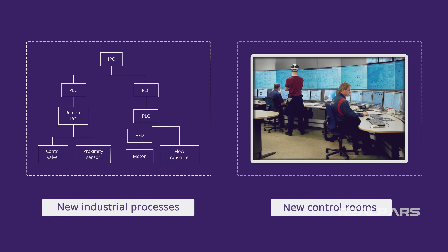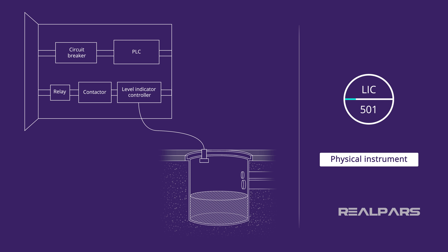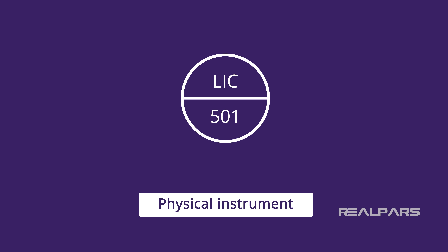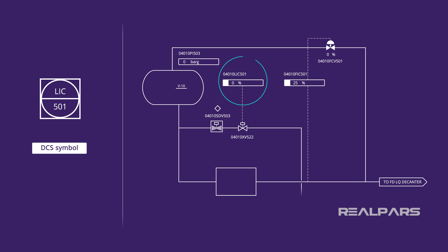So let's look at the P&ID symbols for PLC and DCS. Stand-alone instruments are indicated on a P&ID by a circle with a tag number. The horizontal bar across the middle of the circle indicates the physical instrument resides in a primary location accessible to an operator on the main control panel. If we take that same symbol and draw a box around it, it now means it is no longer a physical instrument — it is now part of a shared display and shared control in a DCS.